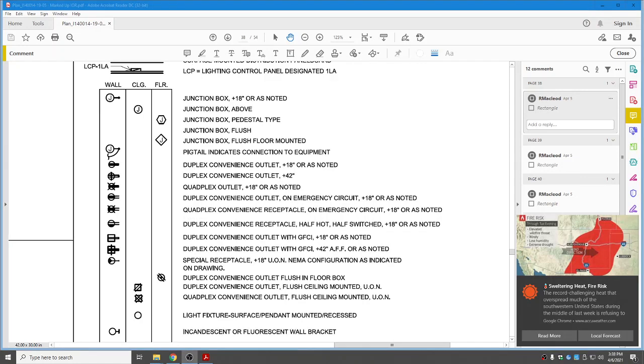Now let's take a look at our electrical on the walls or in the ceiling or in the floor. On the left side, you can see a junction box with a J will typically be at 18 inches, or as noted. If it's above the ceiling, the symbol will look like this, and if it's in the floor, it'll be a hexagon. Let's drop down to a duplex convenience outlet at 18 inches, or as noted. Duplex convenience outlet at 42 inches. A quadplex outlet at 18, or at other heights.